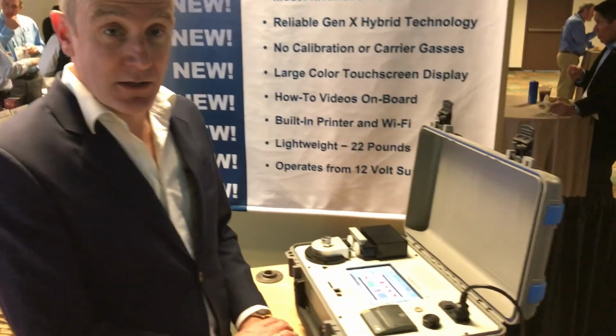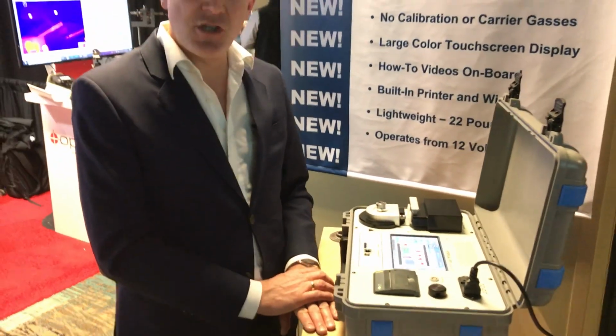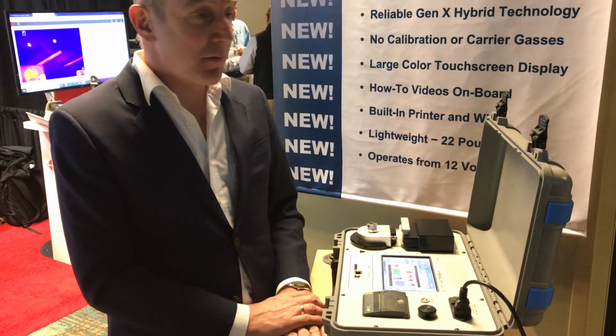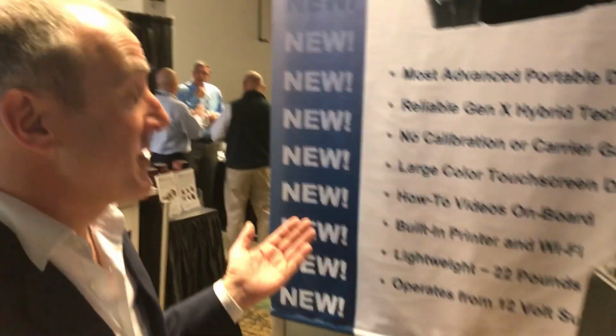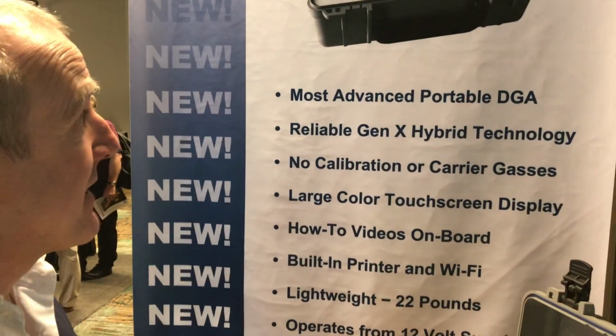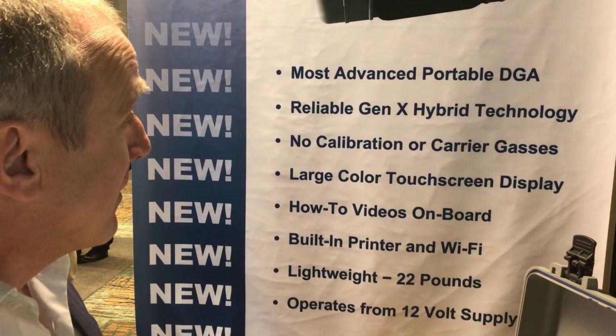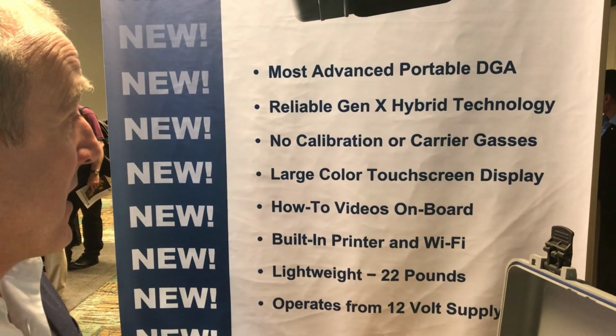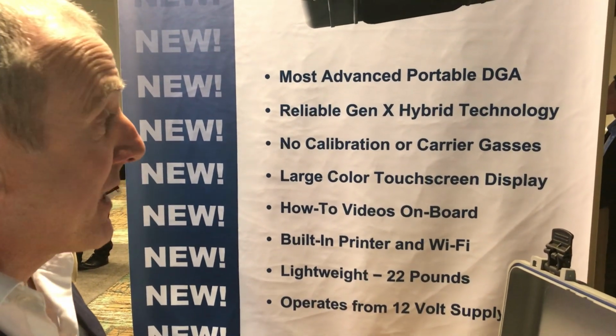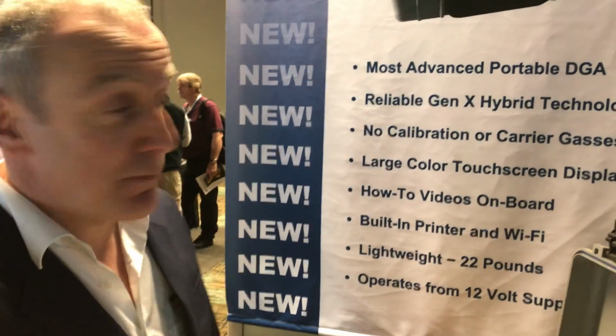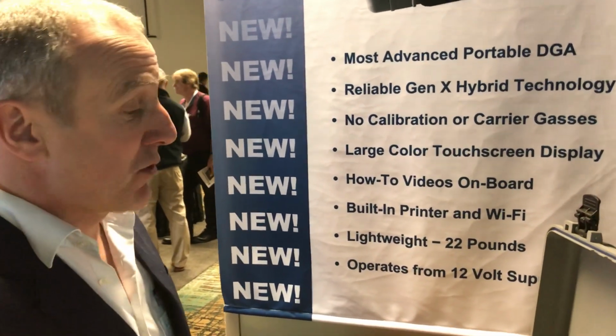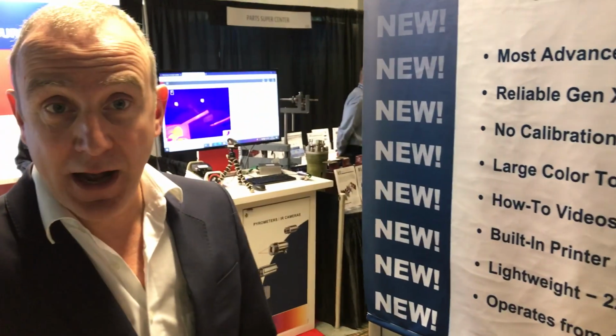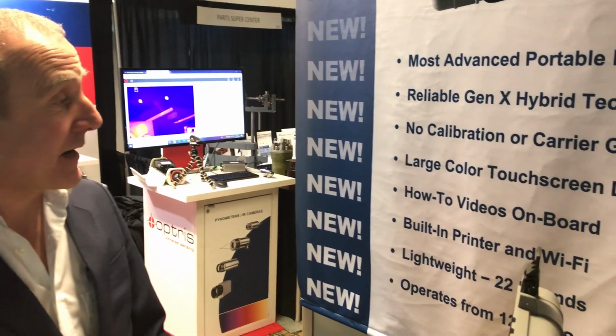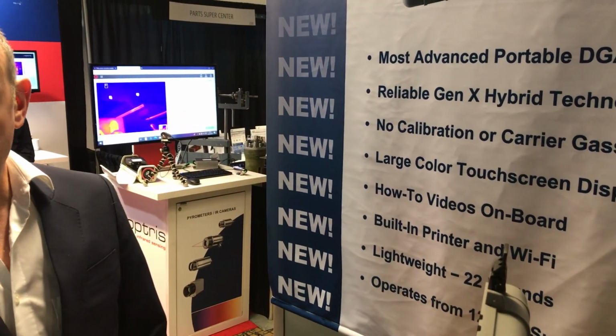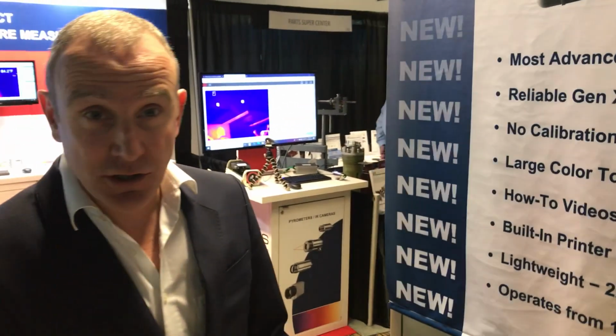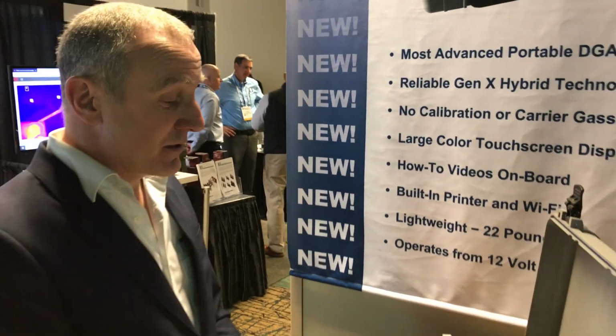This is our brand new H1011 Gen X. It's a portable DGA device, which is probably the most advanced device in the market right now. It doesn't require any calibration or carrier gas because it works on near infrared, optical infrared technology for the gas measurement and headspace extraction for the gas extraction.